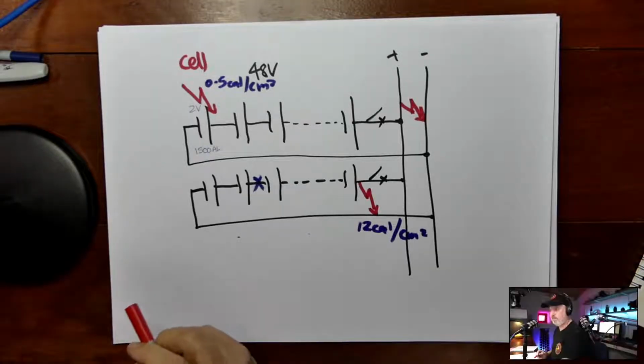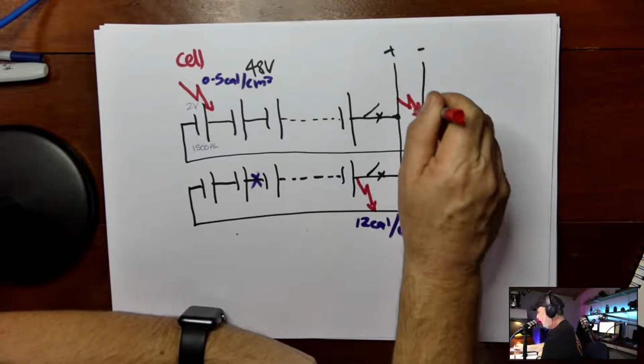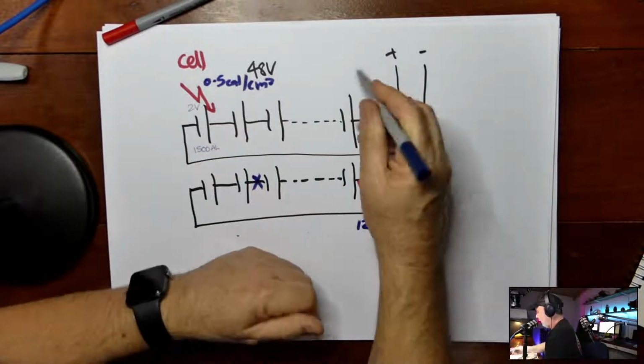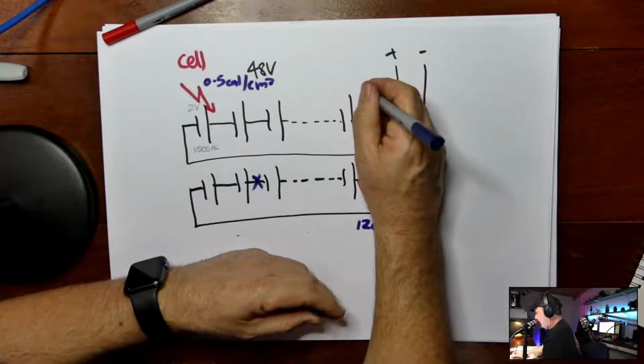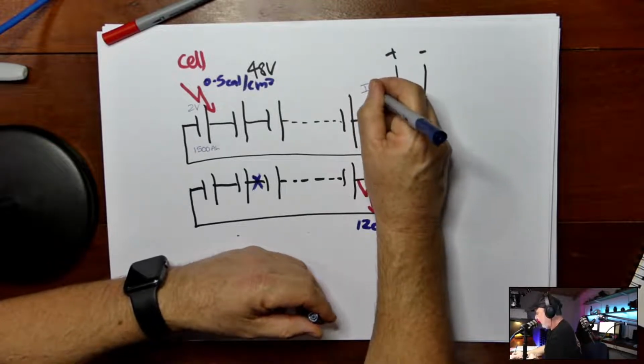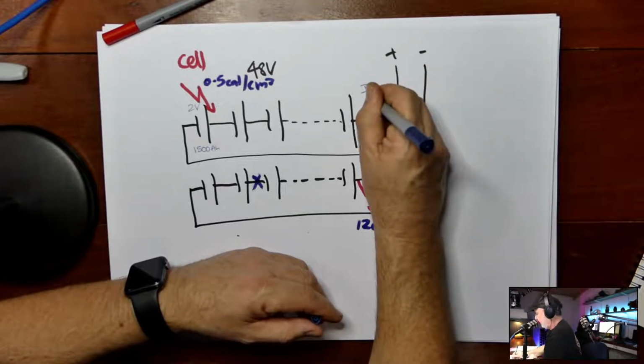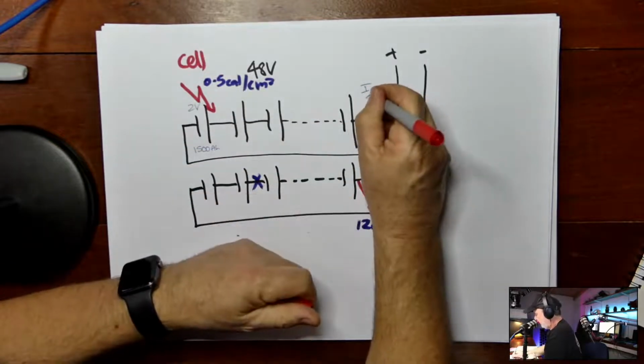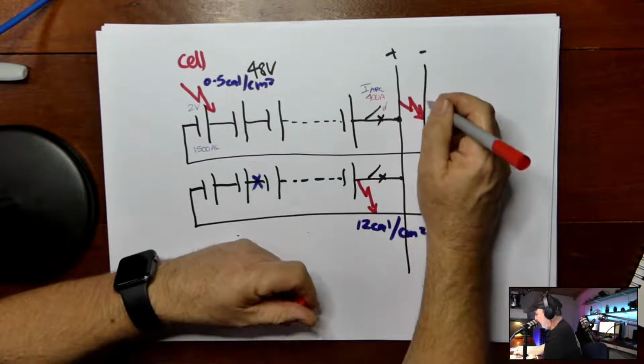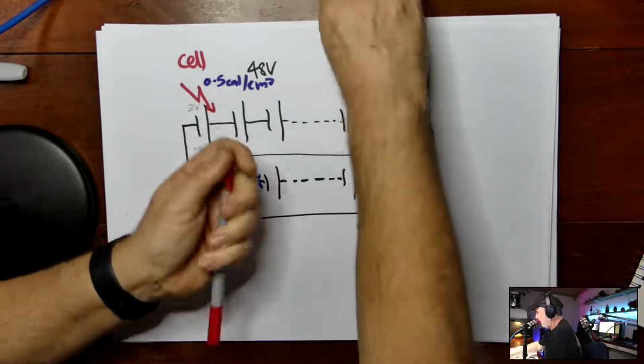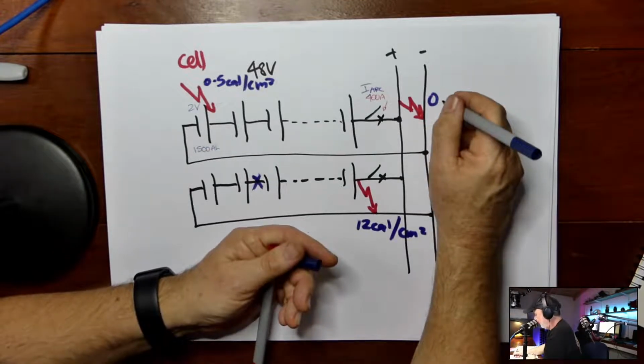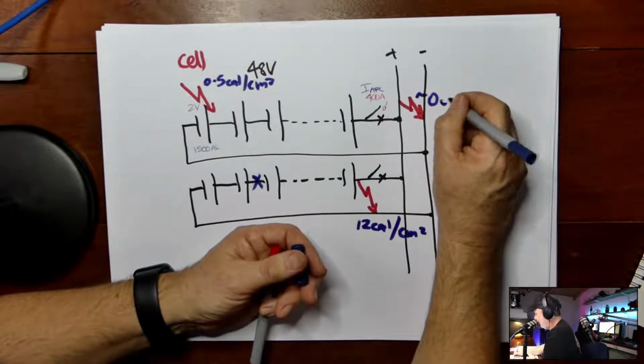Now, I'm just looking to see if I've covered off everything, or if I should go back to my drawing. So just to complete this, because we've got the interstring overcurrent protection devices, and I rated them as 400 amps on each of these. That's when your pen fails on you. There we go. 400 amps. That means that at this point here, our cal is very insignificant. It dropped to approximately naught cal per square centimetre.